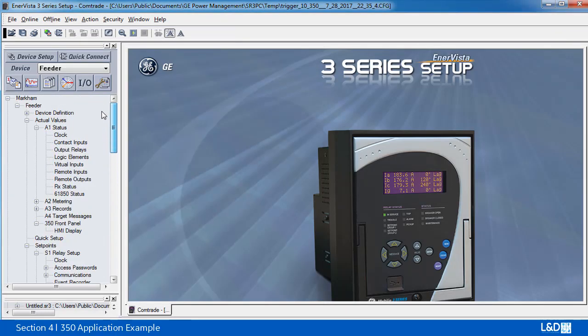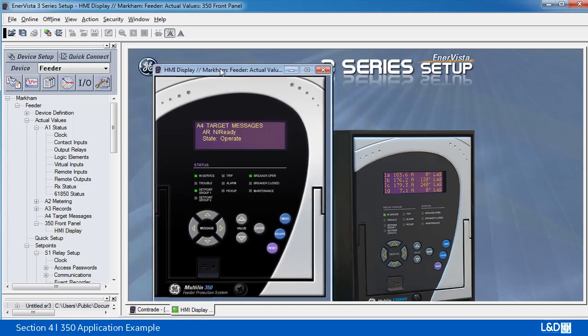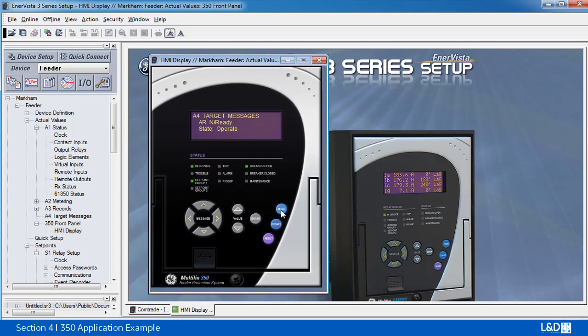I'm going to use the HMI display of the 350 relay to close the breaker. We can use the mouse click instead of pressing the front panel. So I choose the command. We can see that the breaker status, now it's open, so I choose close, set close to yes and press enter, and now I can see the breaker is closed. And from the target message I can see my auto-reclose is ready.